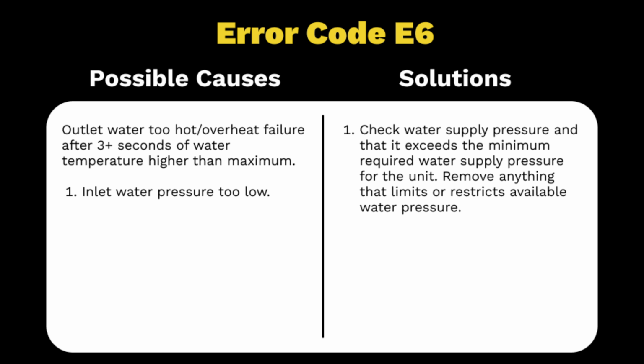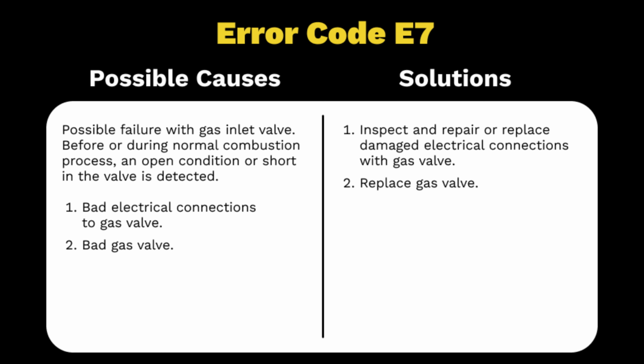If an error code E6 presents, this signifies that the outlet water is too hot. We want to ensure that the water pressure and flow meets the required levels of 1.5 gallons per minute. If an error code of E7 presents, this indicates a possible failure with the gas inlet valve. Ensure that all connections to the gas valve are secured.